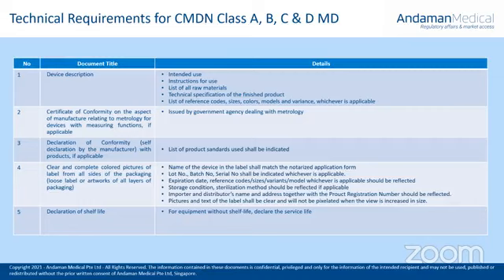Storage condition, so it shall match the one indicated in the IFU of your product. So if your IFU mentions that the product shall be stored at 2 to 8 degrees Celsius, then your label should have the same declaration. Sterilization method. In labels, this is usually presented as a symbol. For example, you will see a symbol of EO, which means the device was sterilized using the ethylene oxide sterilization process. The symbol of R means it was sterilized using the irradiation method. H2O2 means sterilization via vaporized hydrogen peroxide. So when you have this symbol on your label, you have to include the sterilization procedure, validation, and verification report in your submission.